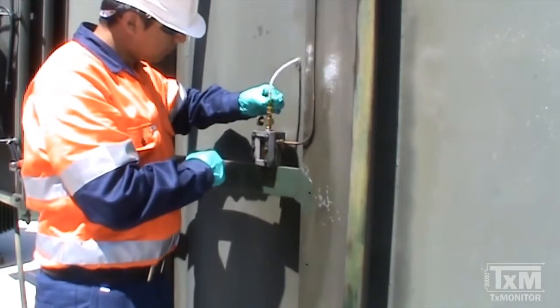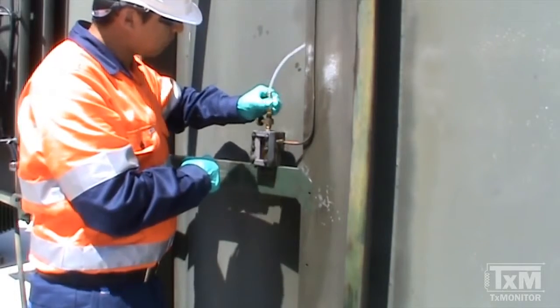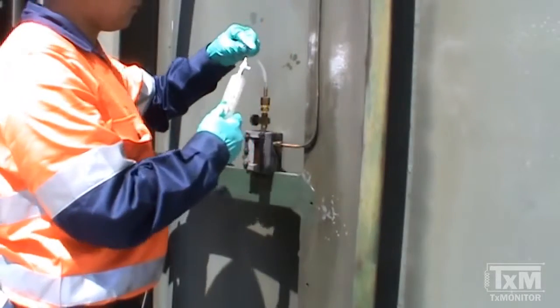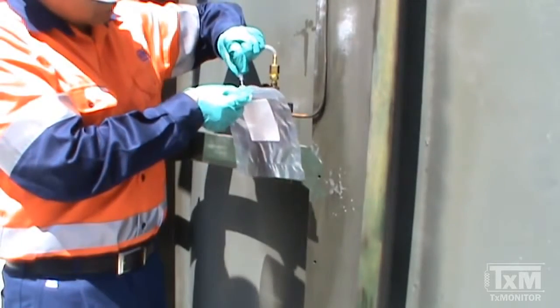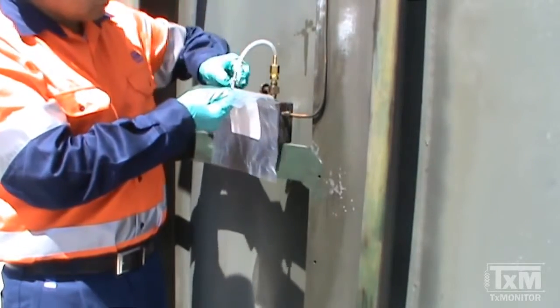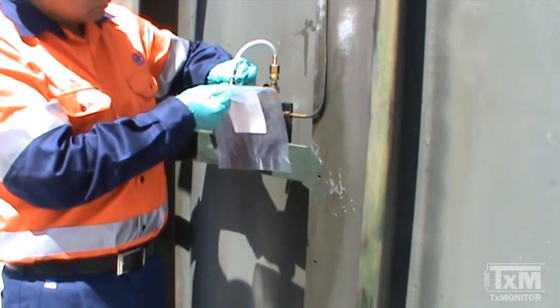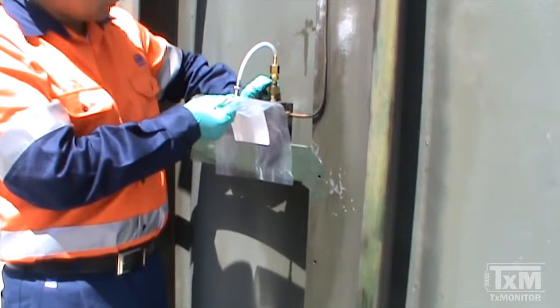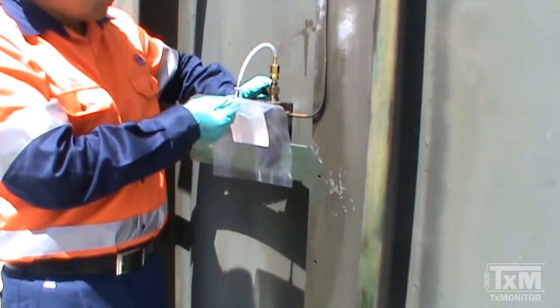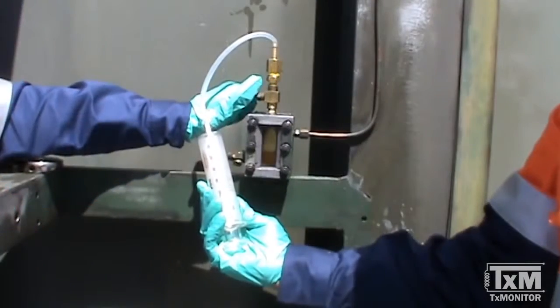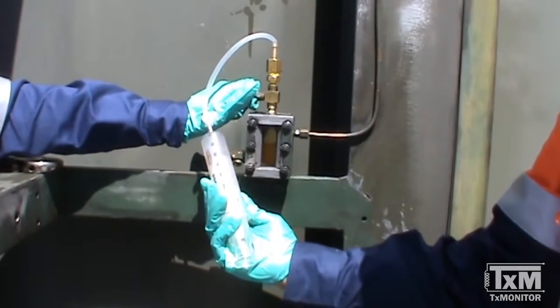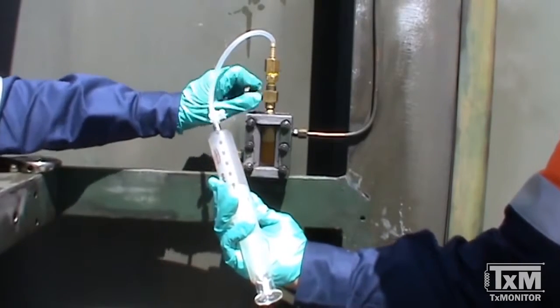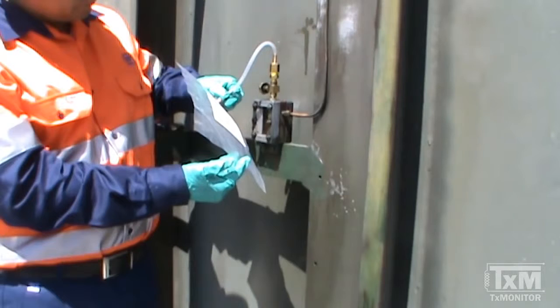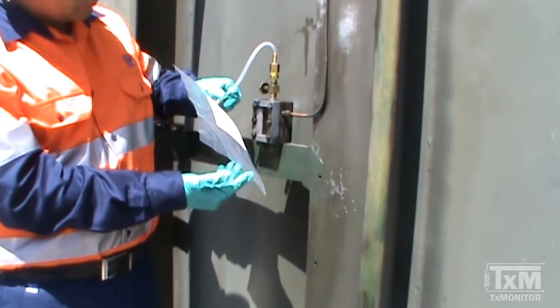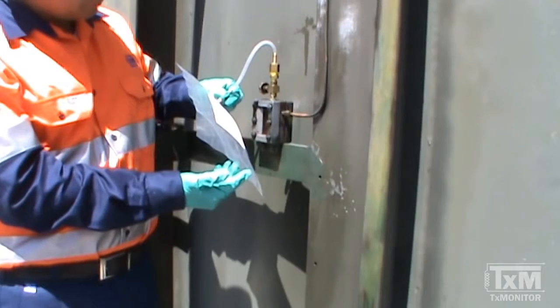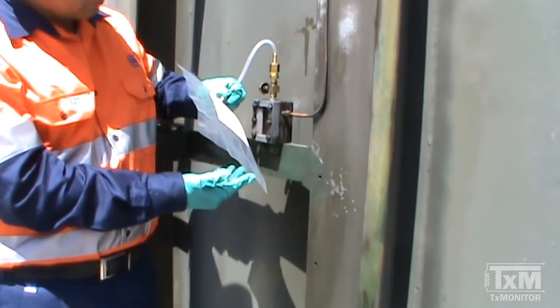Attach the sampling tubing to the top port of the sampling device. Connect the sampling container, either the glass syringe or the sampling bag, to the tubing connected to the top port of the sampling device. Open the valve on the sampling container and then open the top port of the sampling device to allow the gas to flow. You will notice that the oil level will start to rise again as the gas is pushed out of the sampling device. Use additional syringes or bags if necessary to collect all the gas accumulated in the Buchholz relay.